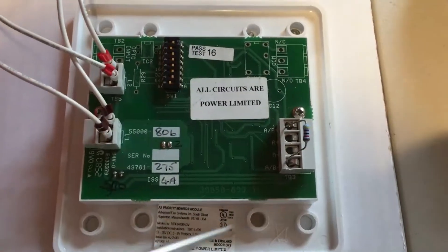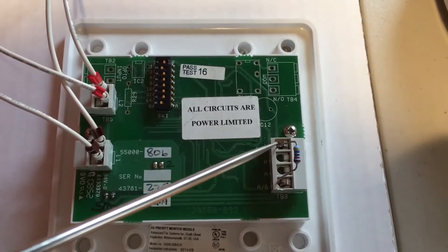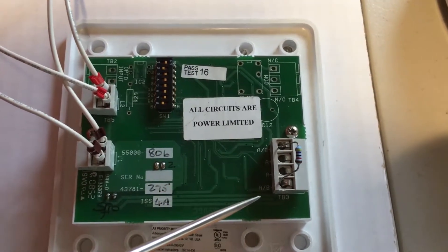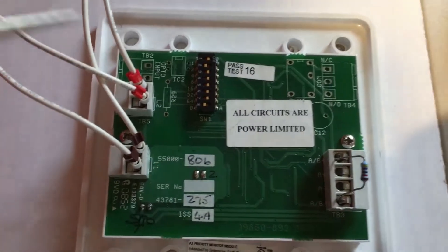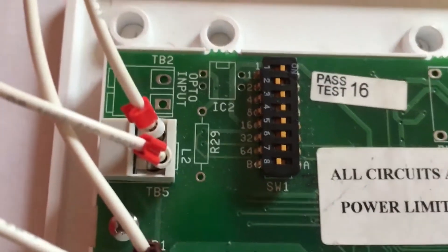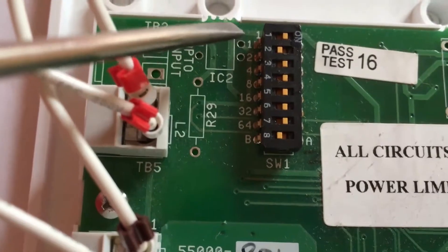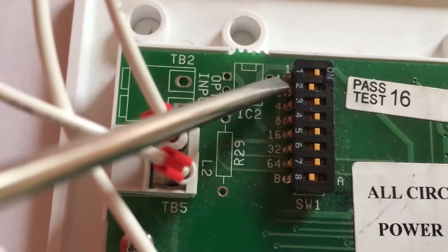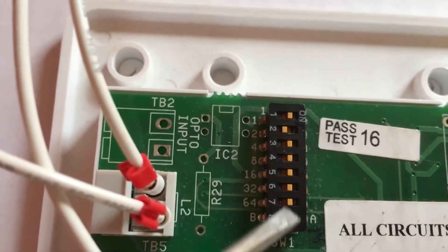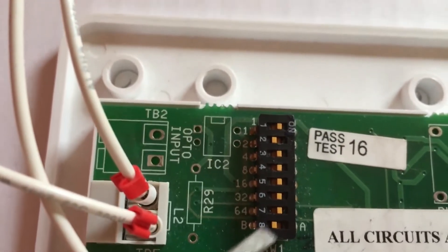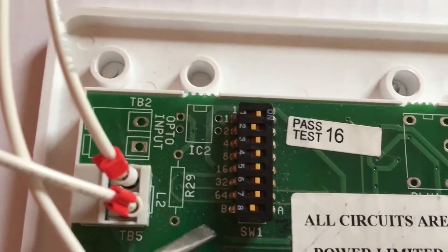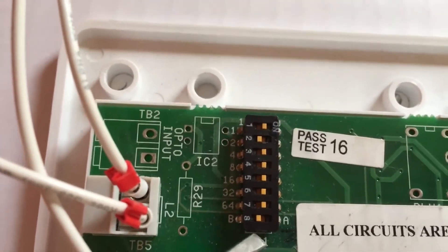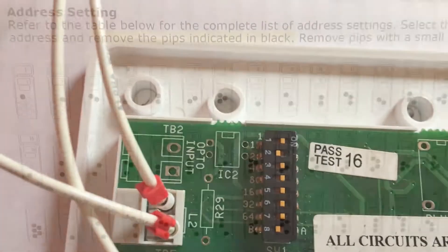Here is our monitor module and you can see here that we've got the inline resistor placed on the B terminals there. Our address for this device was going to be number two and if we look closely you can see that I have set the DIP switch pot number two to the off position, all others are in the on position. Now the final switch, segment number eight, we move the DIP switch so that it's showing to the B side not the A side, class B wiring.